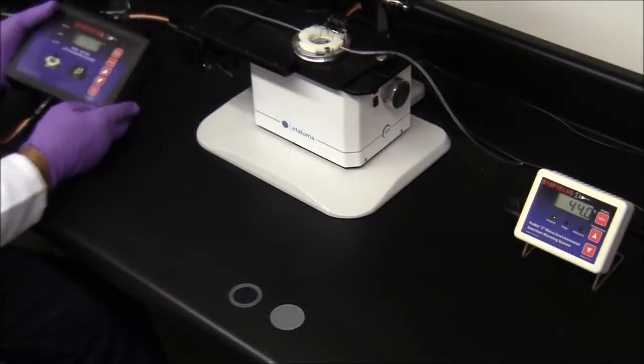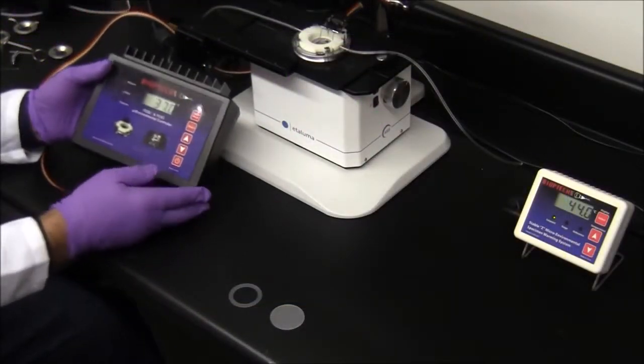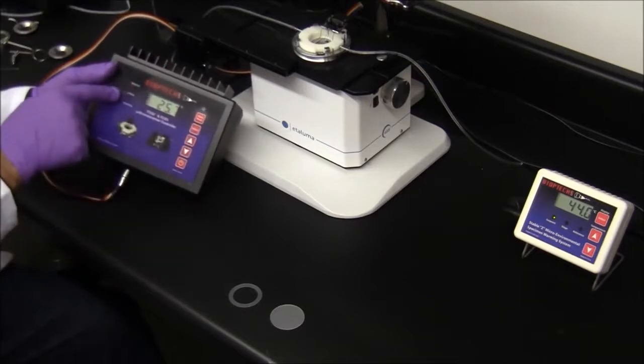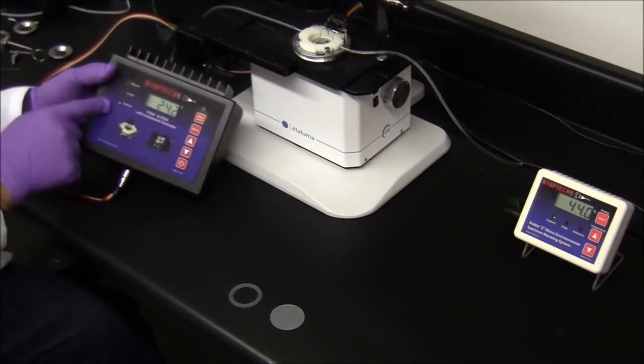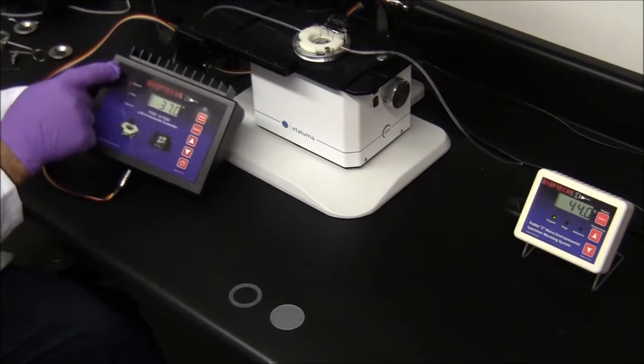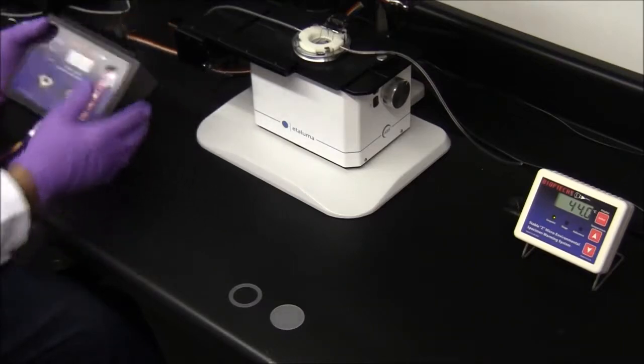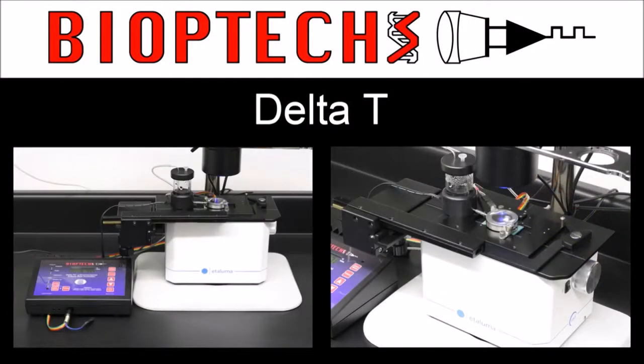The temperature controller is adjustable between ambient and 50 degrees C. It has a fast-acting channel for the microaqueduct slide and a second channel for the chamber base. Here we have a Delta T system on an Etaluma microscope.